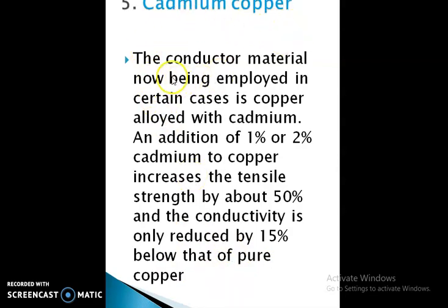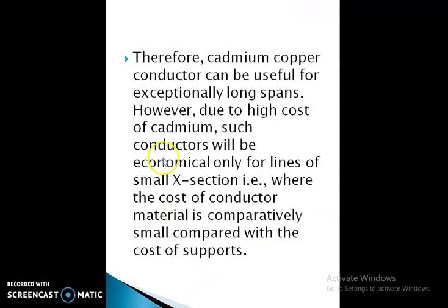The fourth type is cadmium copper. The conductor material now being employed in certain cases is copper alloyed with cadmium. An addition of one to two percent cadmium to copper increases the tensile strength by about fifty percent, while the conductivity is only reduced by fifteen percent below that of pure copper. Therefore, cadmium copper conductors can be useful for exceptionally long spans. However, due to the high cost of cadmium, such conductors are economical only for lines of small cross-sections, where the cost of conductor material is comparatively small compared with the cost of supports.